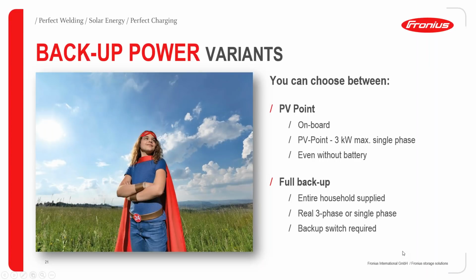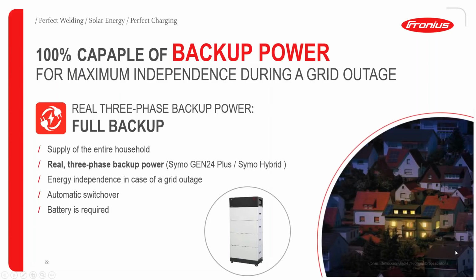And we have talked about the backup power variants. That's a feature you can use, but there are again 2 options you can choose. We have the full backup I showed you in the schemes already, where you can supply the entire household, and you need this additional backup switch gear. But what is also very specific about the Gen 24 Plus series is the basic backup power function: the PV Point, which is standardized on board, 100% free of charge, and which also works even without a battery. That means this is a socket in your household where you can supply on a single phase up to 3 kilowatts max, depending on your current PV generator production.